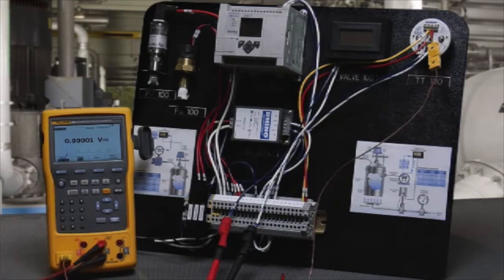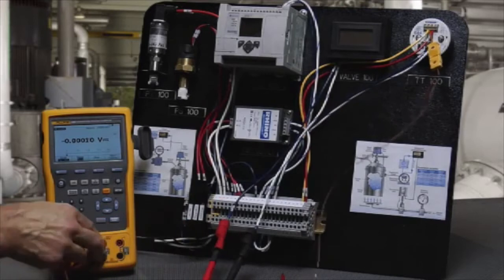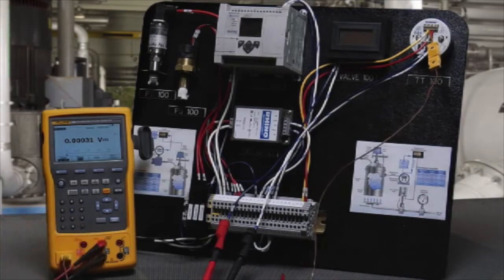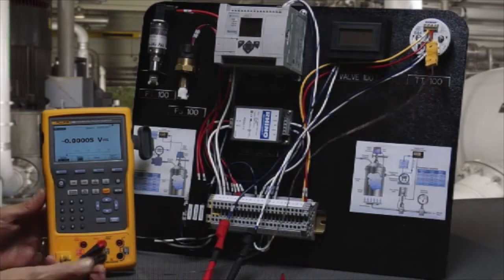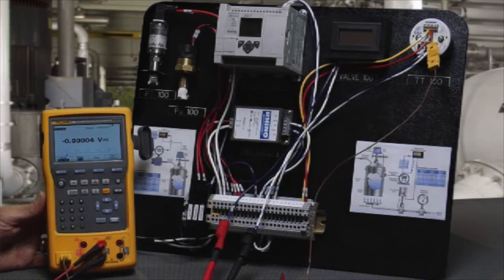We're going to measure the milliamp signal of the transmitter on the input of the 754 and power it with a 24-volt power supply internal. We're going to source or simulate a temperature signal to the input of the transmitter while simultaneously measuring the milliamp output and calculating error percent of span.